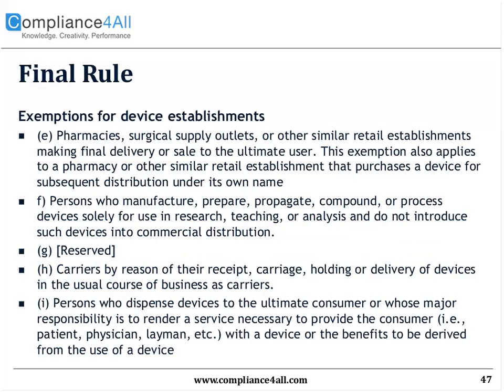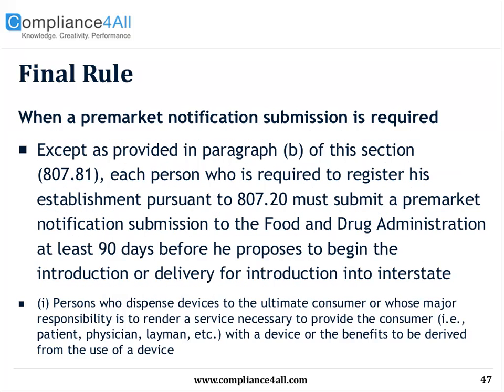Other exemptions for device establishments include pharmacies, surgical supply outlets, or other similar retail establishments making final delivery or sale to the ultimate user. This exemption also applies to a pharmacy or other similar retail establishment that purchases a device for subsequent distribution under its own name. F, persons who manufacture, prepare, propagate, compound, or process devices solely for use in research, teaching, or analysis and do not introduce such devices into commercial distribution certainly would not have to register and list. They would be exempt. And others, as stated, include carriers by reason of their receipt, carriage, holding, or delivery of devices in their usual course of business as carriers, or persons who dispense devices to the ultimate consumer, or whose major responsibility is to render service necessary to provide the consumer, that is, the patient, physician, and so forth, with a device, or the benefits to be derived from the use of a device.